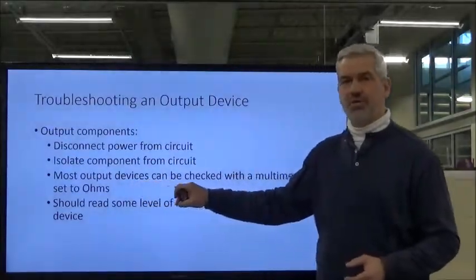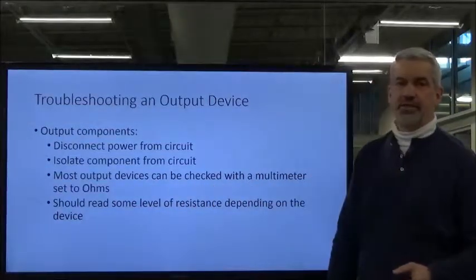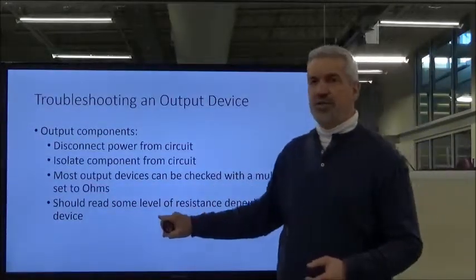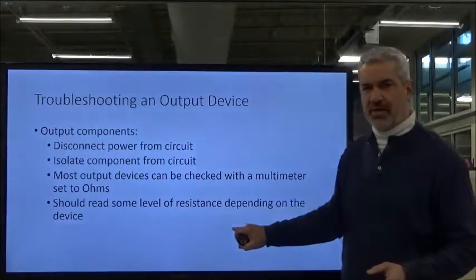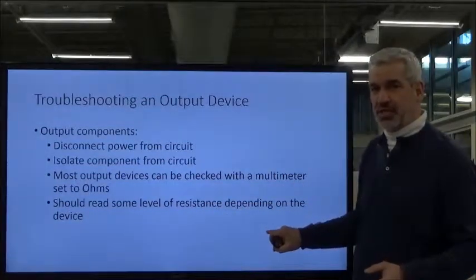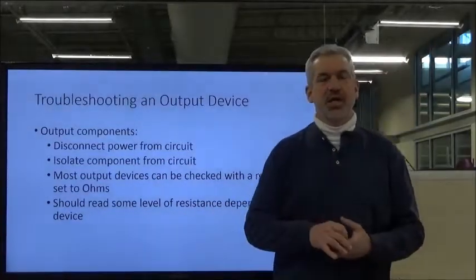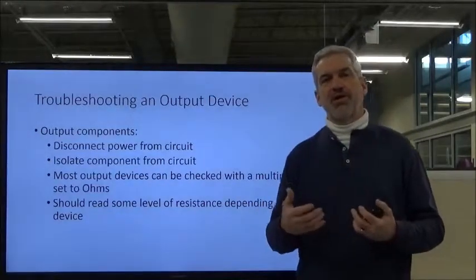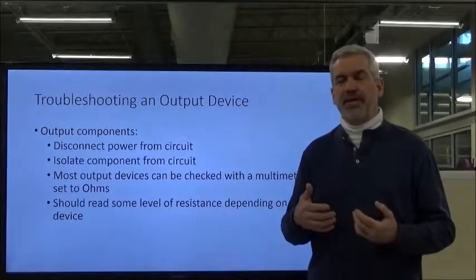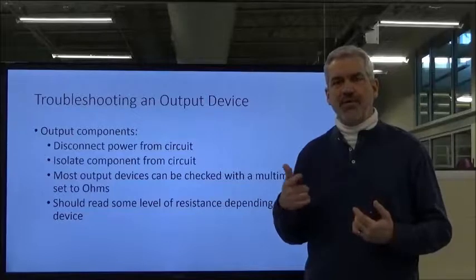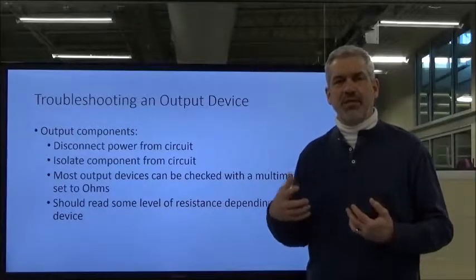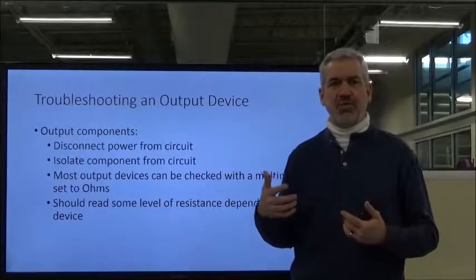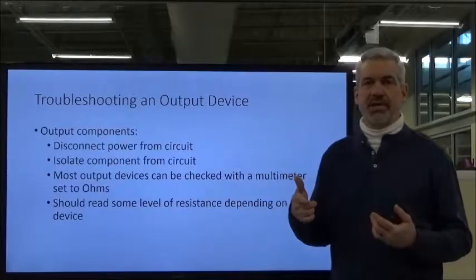We'll also use an ohm meter to check this. However, you should be reading some amount of resistance—this will not just pass it through. For example, on relay or motor starter coils, there's quite a bit of winding, so there's some resistance because of the length of wire it takes to make a coil.